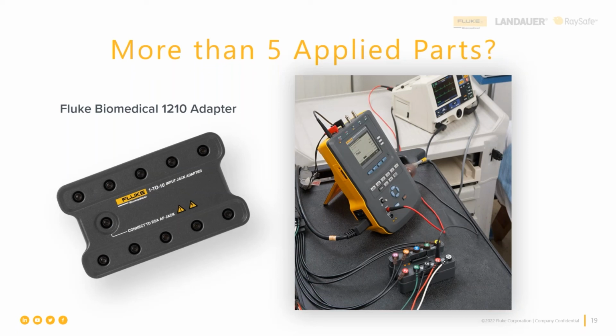And so we provide this 1 to 10 adapter that allows you to short together things like the 10 leads coming from the bigger ECG cable from 12 lead carts as well as defibrillators. And then you still have some lead posts at the top that you can use for pads or paddles. And if there were extra or separate pacing test leads, you would be able to connect those as well and properly run the entire test, having made your connections just once.